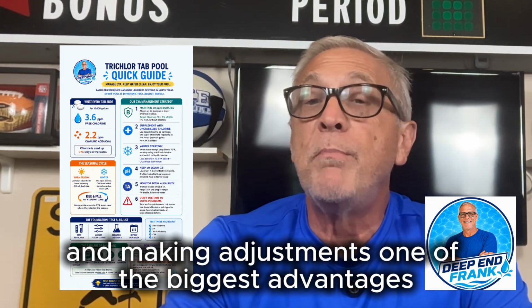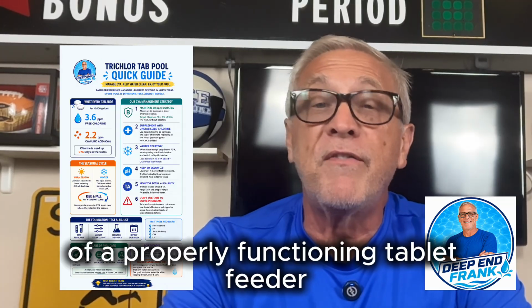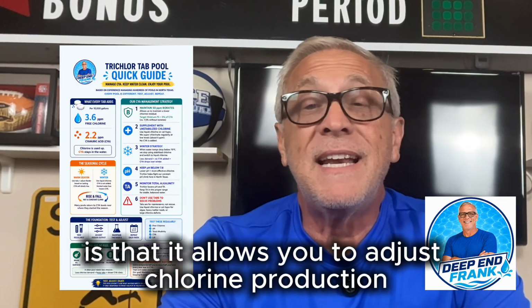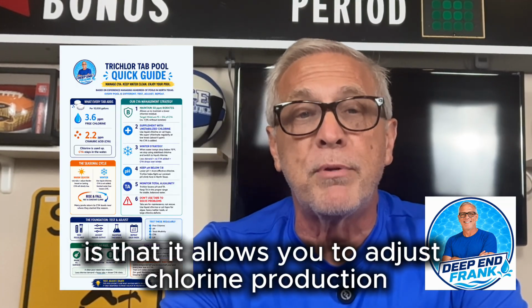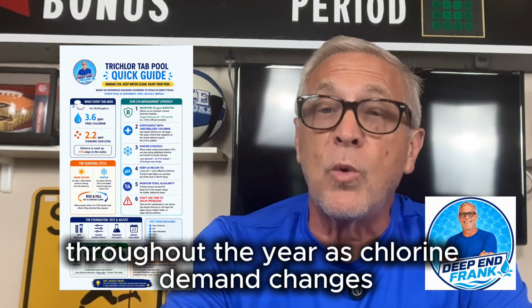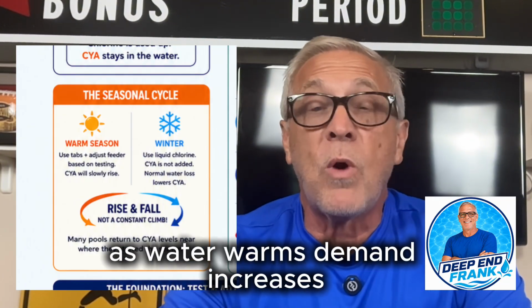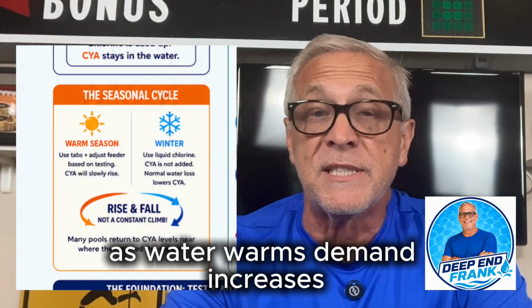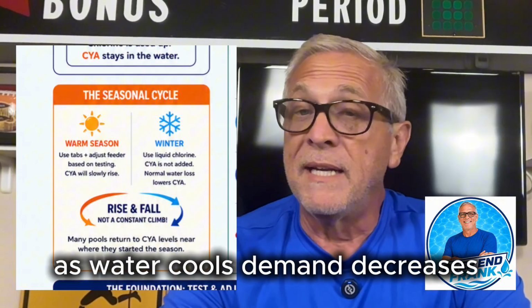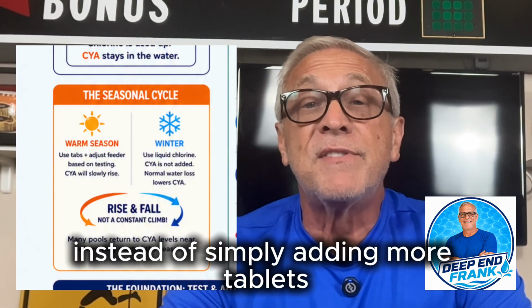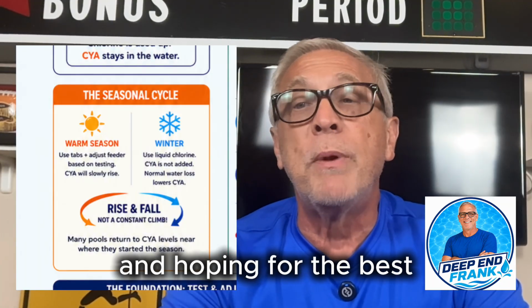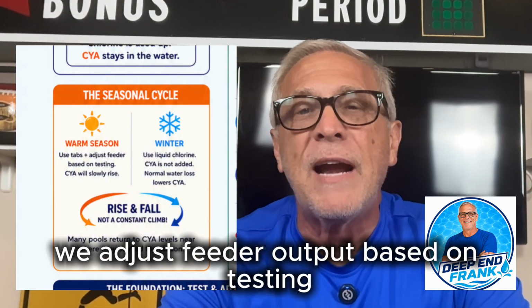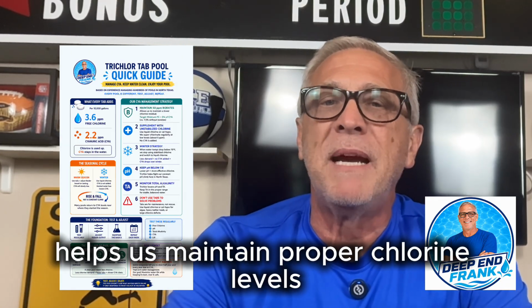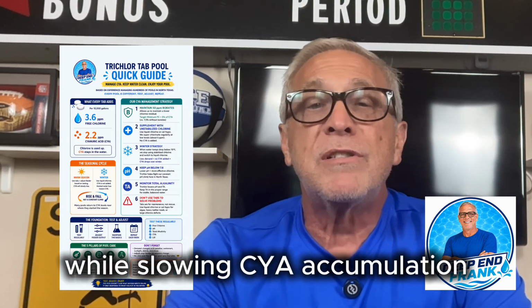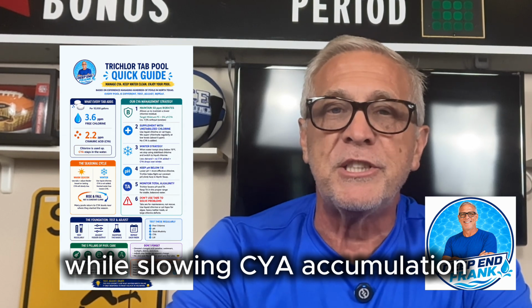One of the biggest advantages of a properly functioning tablet feeder is that it allows you to adjust chlorine production throughout the year as chlorine demand changes. As water warms, demand increases. As water cools, demand decreases. Instead of simply adding more tablets and hoping for the best, we adjust feeder output based on testing. That simple practice helps us maintain proper chlorine levels while slowing CYA accumulation.